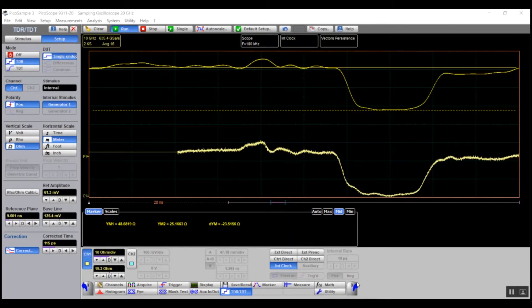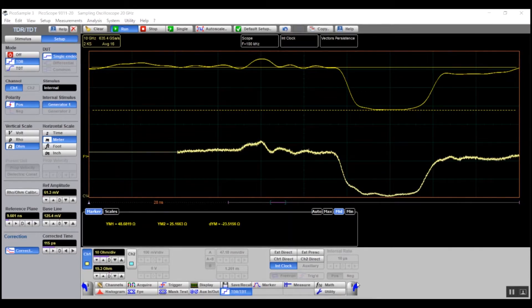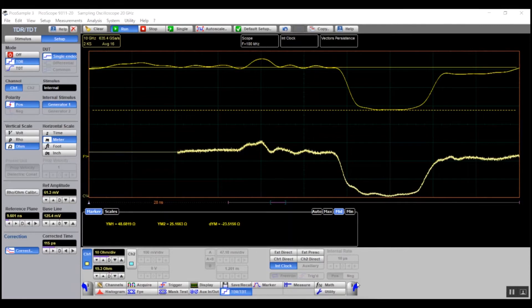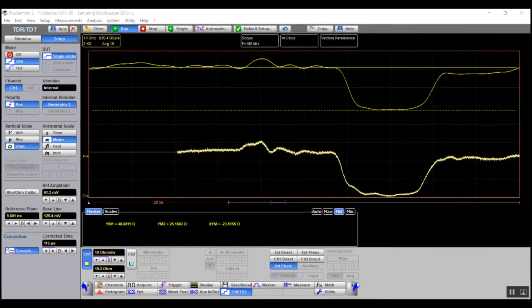Depending on the test, the vertical scale can be defined in volts, gain, rho or ohm. In this example, we are using ohm. The horizontal scale can be specified in time or distance with different dielectric properties of the transmission line.